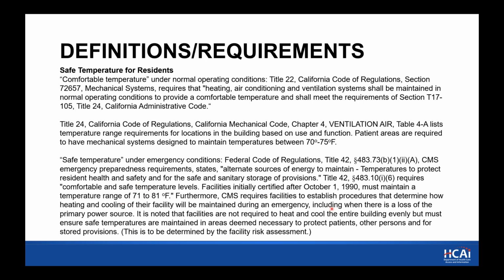Furthermore, CMS requires facilities to establish procedures that determine how heating and cooling of their facilities will be maintained during an emergency, including when there's a loss of primary power source. It is noted that the facilities are not required to heat and cool the entire building evenly, but must ensure safe temperatures are maintained in areas deemed necessary to protect patients, other persons, or for stored provisions. This is to be determined in your specific facility risk assessment. As of right now, we are identifying a safe area for temperatures as the patient care or resident care areas. If other solutions are going to be proposed, include them in the assessment, and those will be looked at individually.